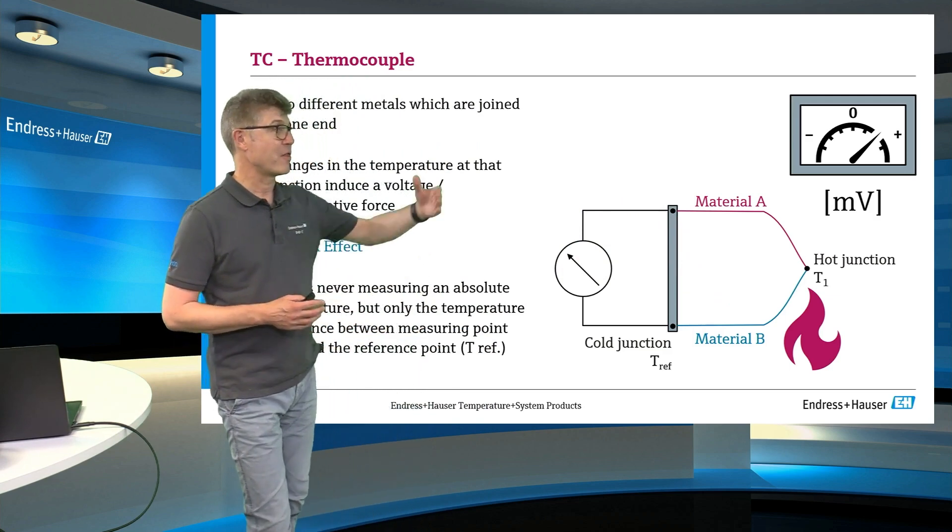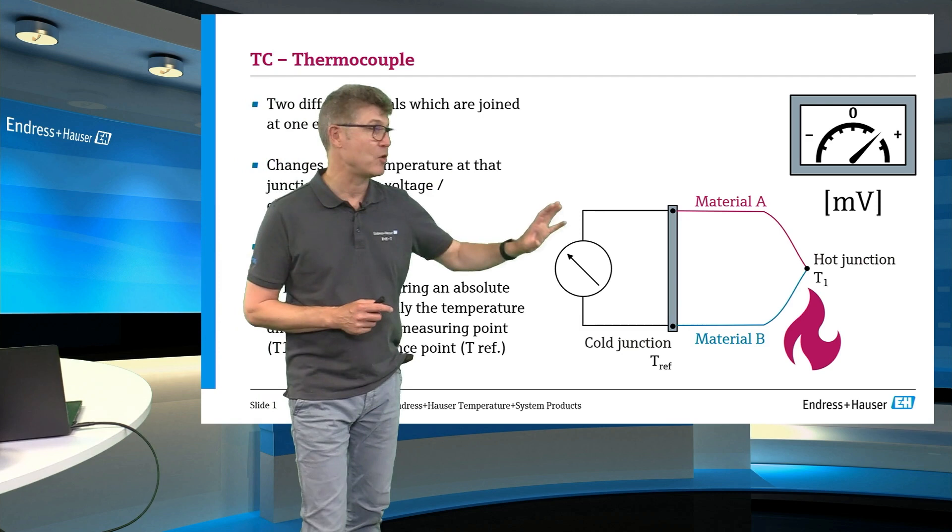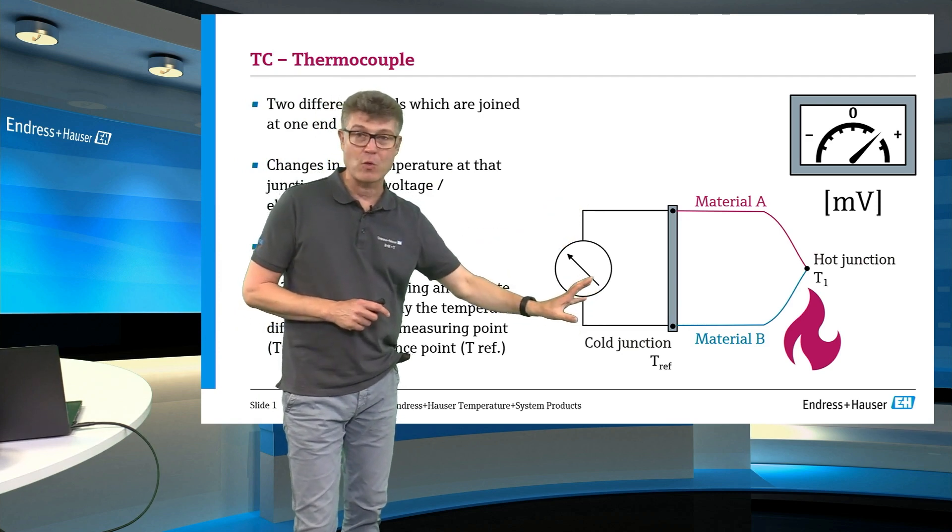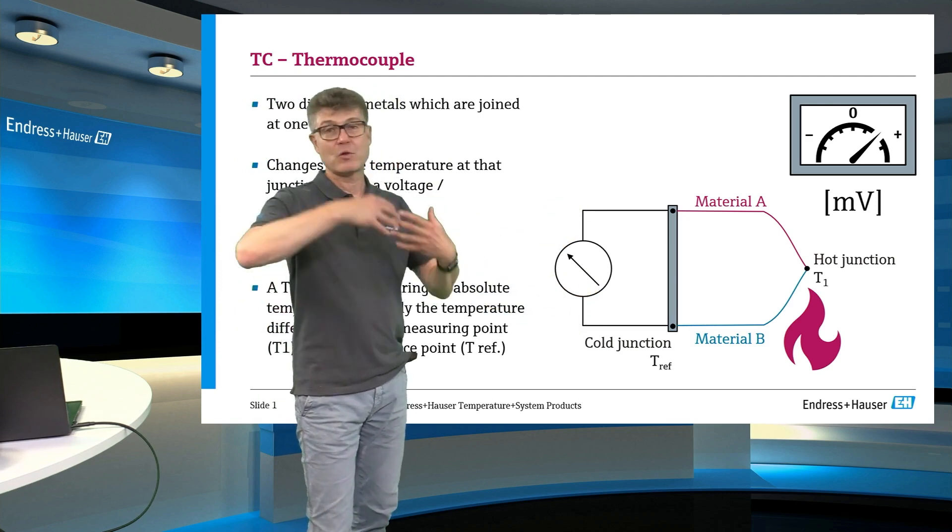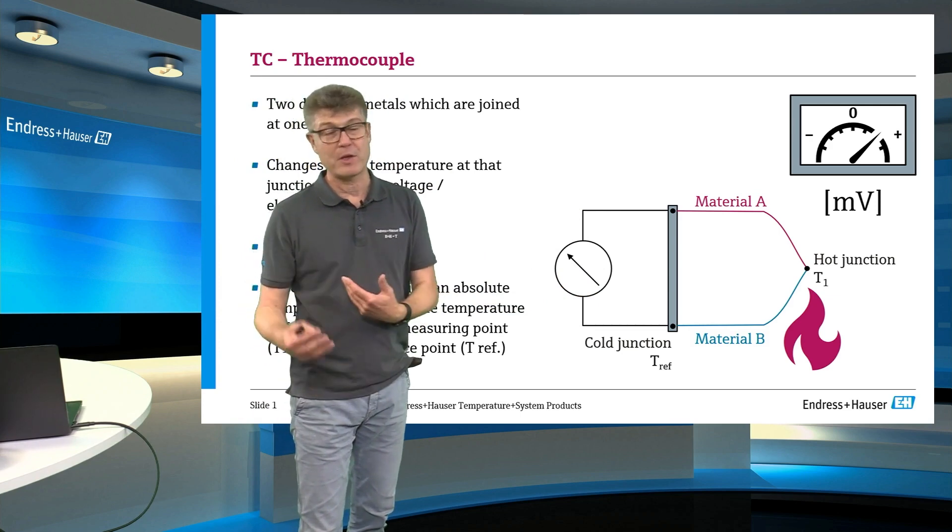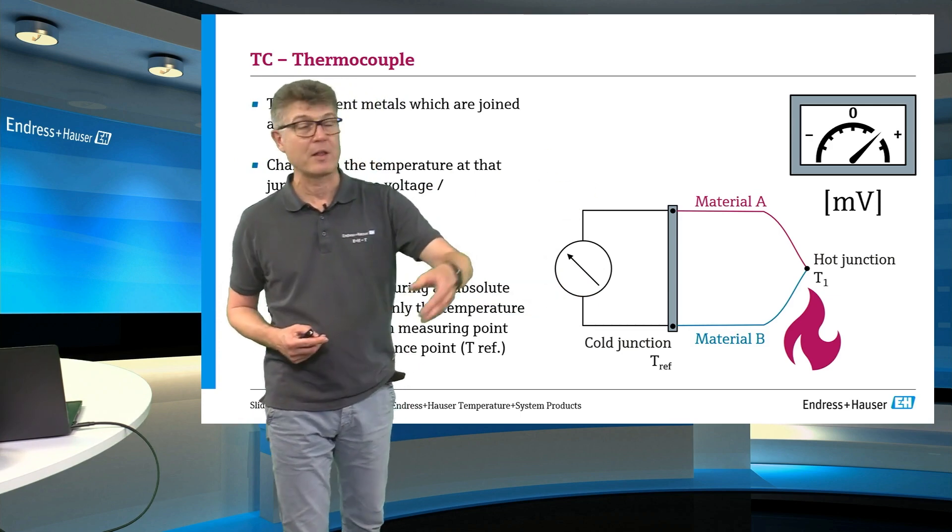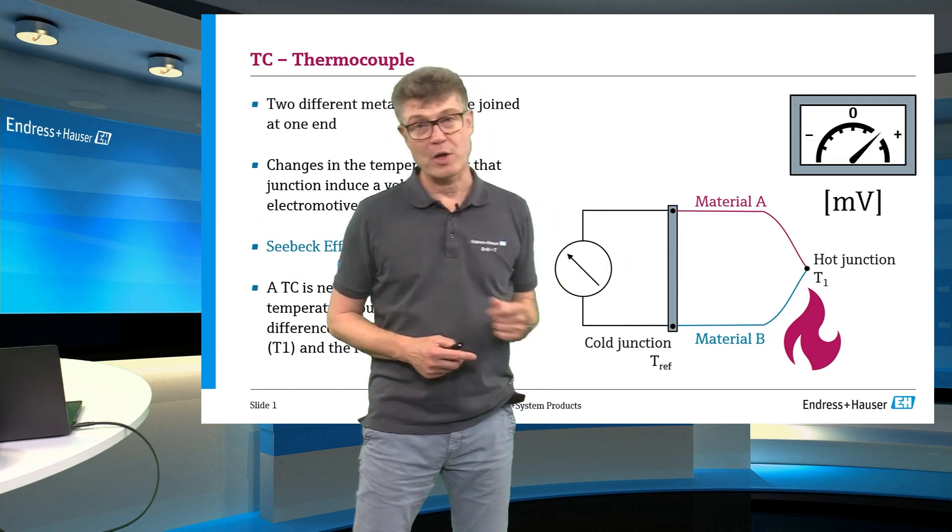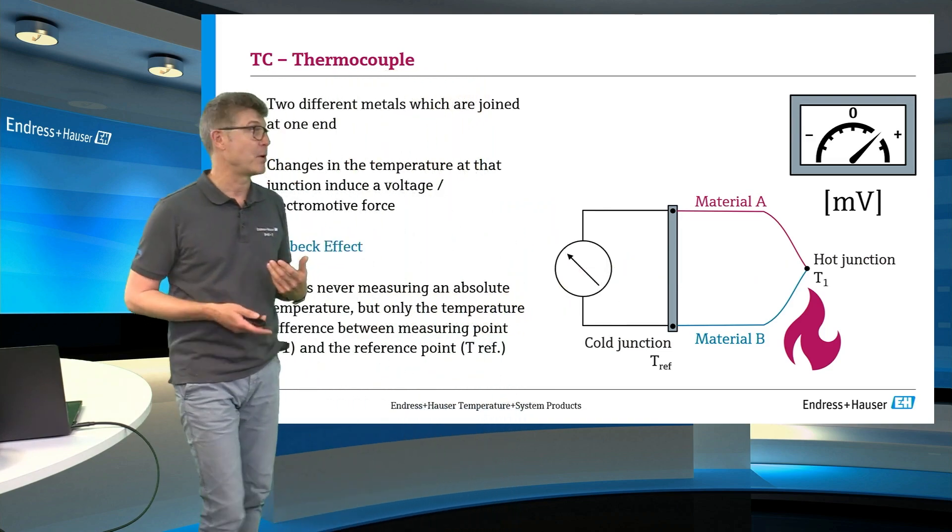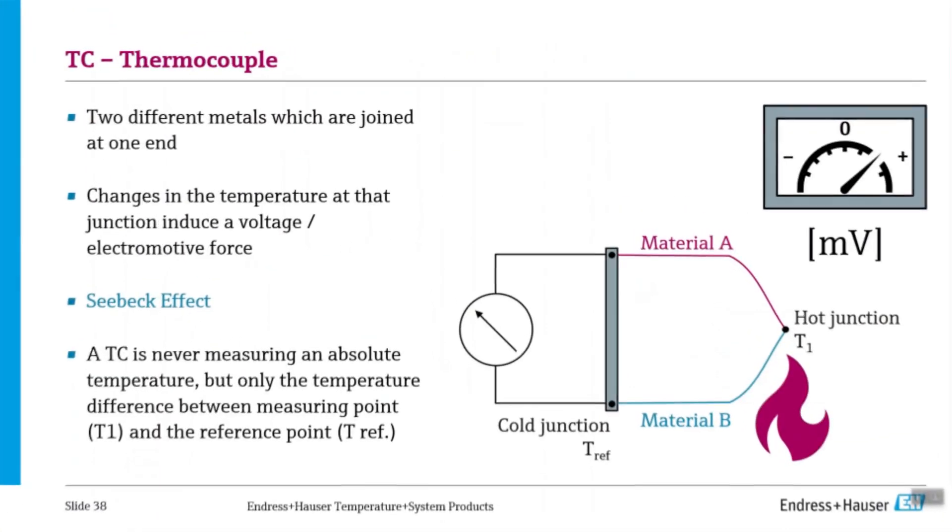And so, to measure the real temperature, we need to know the temperature of the cold junction. We need to know the characteristic curve of the material and then we can calculate what is the temperature at the hot junction. This is a general principle of a thermocouple measurement.